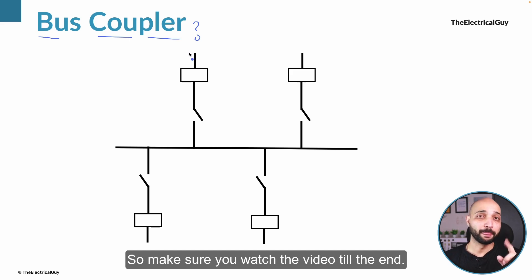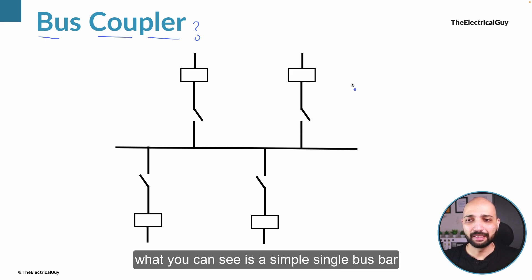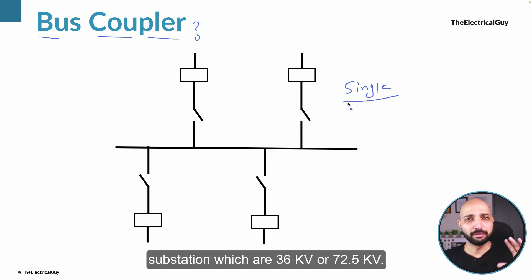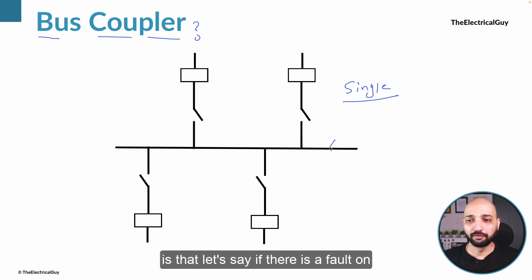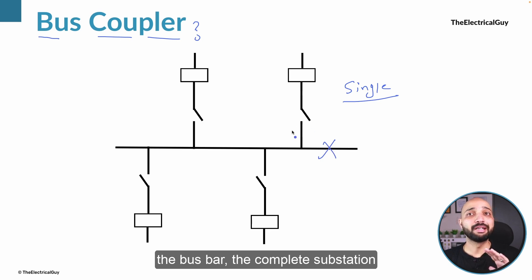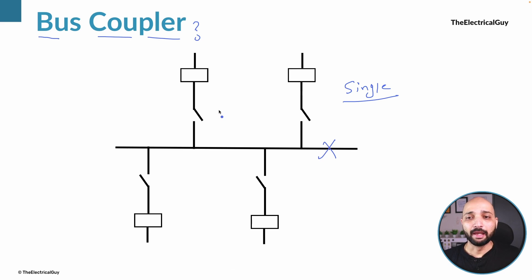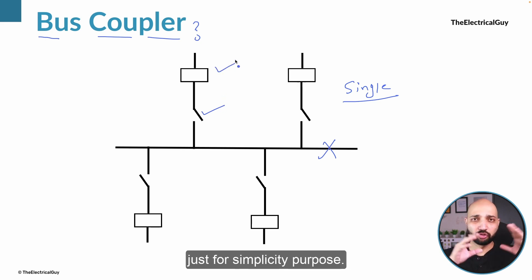So on the screen right now what you can see is a simple single bus bar arrangement that is generally used in substations which are 36 kV or 72.5 kV. Now the problem with this type of arrangement is that if there is a fault on the bus bar, the complete substation is going to face that impact — the complete substation is going to go off. Here I have only shown a disconnector and circuit breaker just for simplicity.